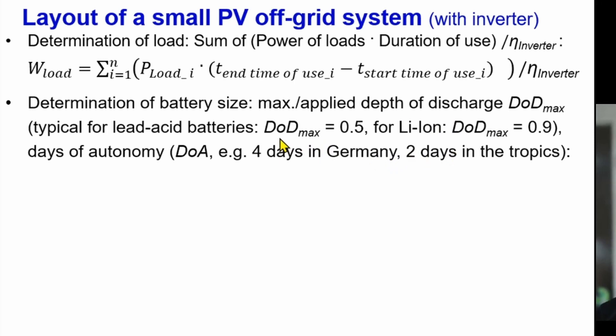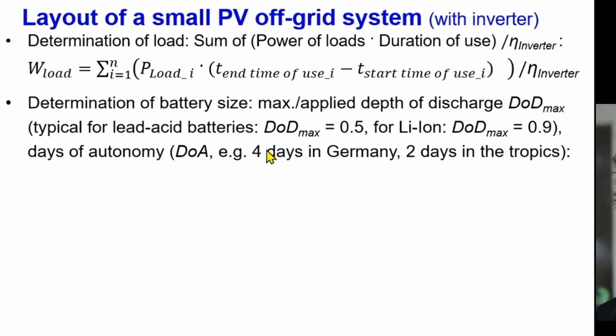The maximum applied depth of discharge for a lead-acid battery is typically 0.5. Lithium-ion batteries are more expensive but can be discharged to a much larger extent, though their lifetime is also reduced. We also consider days of autonomy — how many equivalent days without irradiance the system must handle. In the tropics, two days is sufficient; in Germany, there can be long low-irradiance periods equivalent to four days without irradiance.